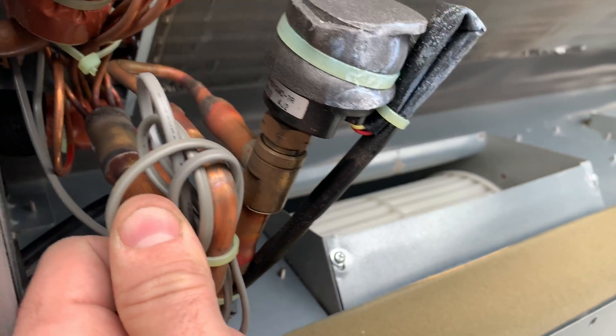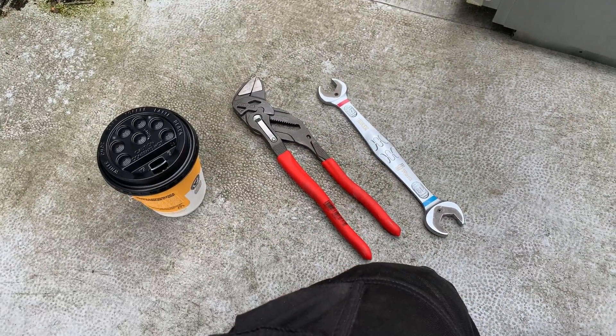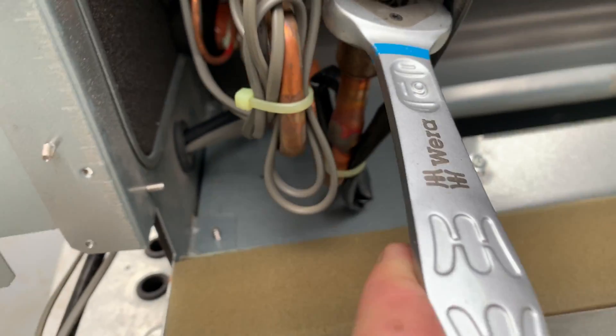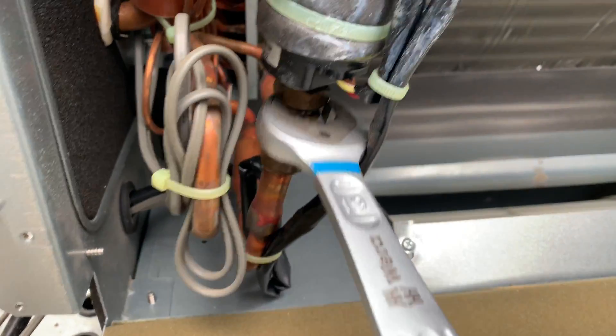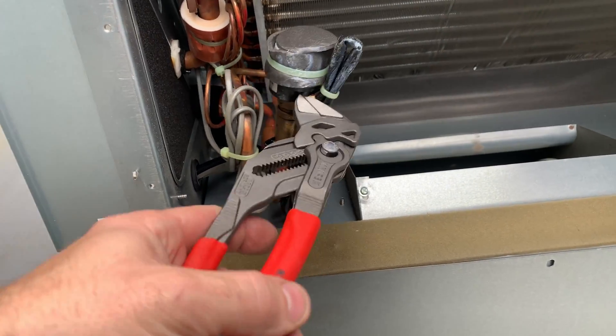We've got a couple of tools and a coffee. 19mm - that's going to get you around the LEV motor head, so you see that sort of nut in there? You can use a 19mm on there, and then if you look at the body itself, it's got flat sides. I've just grabbed a Knipex pliers wrench to hold the body tight.